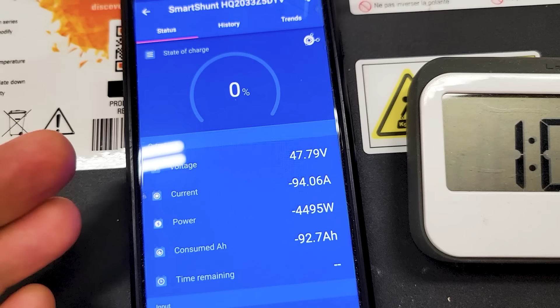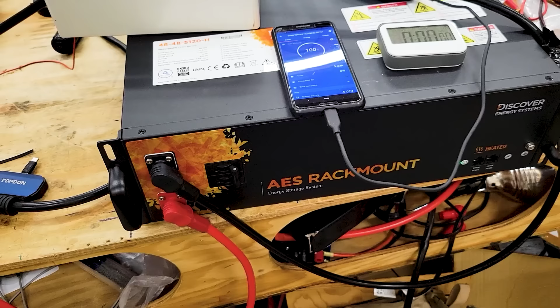Well, we made it: 1 hour of continuously running at just under, now we're at 94 amps, fluctuating between 92 and 94 amps, keeping us below the 95 amp rating.